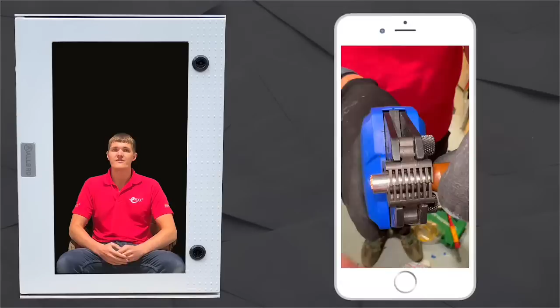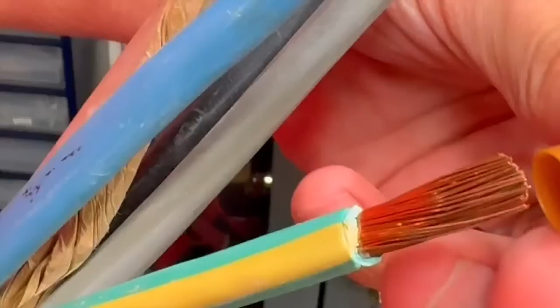The wrong-sized ferrule? What are the chances? Here's the plug I made up in that video, and here's the cable. Look at the side of the cable - it's a 5-core, 25mm squared conductor size. Go to our ferrule colour code chart and select the right one - we use the German Weidmüller system and try to stick to that. Scrolling down the chart to 25mm squared, it's a brown ferrule, and it doesn't conflict with any of the other ones in that system. Go to our selection of ferrules - here we go, and it fits snugly onto the cable. It may have looked a little slack because the camera was so close in, and because of the different profiles that can form when crimping a ferrule.